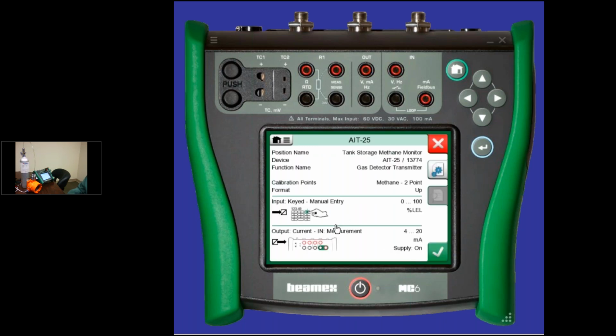So that's kind of a helpful reminder. And then just like you saw with Roy, we're going to be keying in either 0 or, in this test, 50% for the bottle. And we'll be looking for 4 and 12 milliamps on the output. So the range of this transmitter is specified this way. And if it was an indicator, the earlier question, this lower part would say keyed. So if it was an indicator, or maybe we were doing a loop test into the control system, this would say keyed, and as you're exposing it to the air or to the methane bottle, you would key in what is the actual reading. So instead of saying 4 to 20, it would say 0 to 100% LEL here, and you would just key in the reading. So you can do documentation with a keyed input and a keyed output.